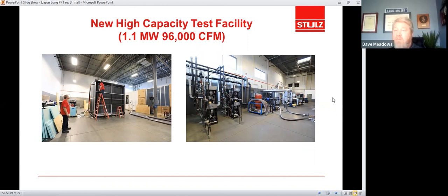We're able to test units up to 1.1 megawatt of cooling, so well over 300 tons and up to 96,000 CFM. One of the great advantages to having this test laboratory for us is that we can take the test data and then apply it to our models that we use to determine performance of the HVAC equipment. And it basically allows us to fine tune those models to ensure that what we're telling our customers they're going to get, they actually get.